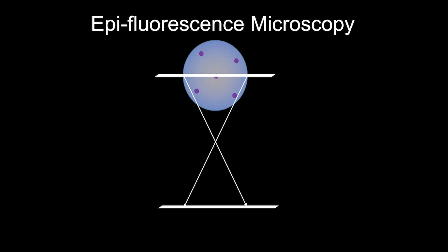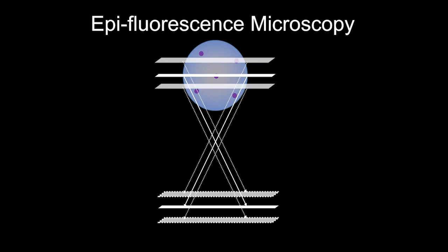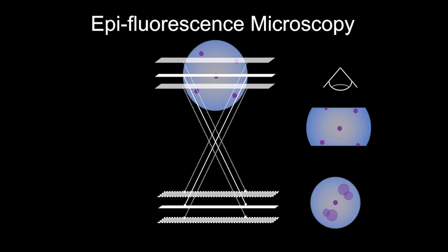So when you want to image thicker samples, most people come and ask for confocal. In epifluorescence, the objective focuses on one plane in a thick sample, but light from other planes also hits the detector — unfocused — creating blur. You get a really fat optical section; the fluorophores above and below your focal plane contribute blurred light. Confocal microscopy was born to solve this.